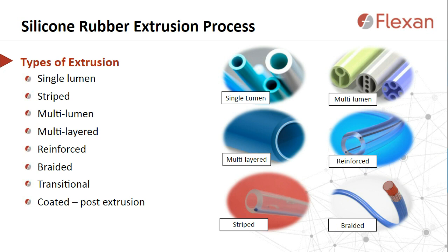Multi-lumen tubes are extrusions that contain multiple channels or passages through the length of the tube. Multi-lumen tubes are commonly used in medical applications where multiple segregated paths are needed for individual devices. The multiple channels can provide a separate path for air to inflate a balloon or segregate delivery or drainage. They can also provide a delivery path for small devices like cameras and wires when minimally invasive procedures are required.